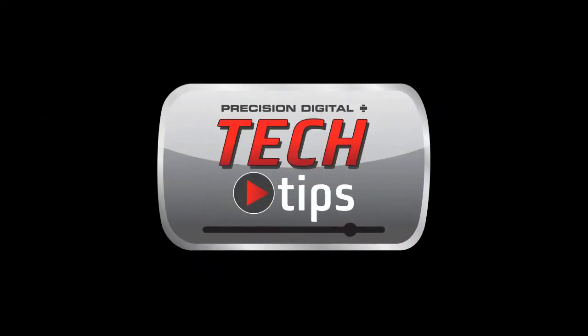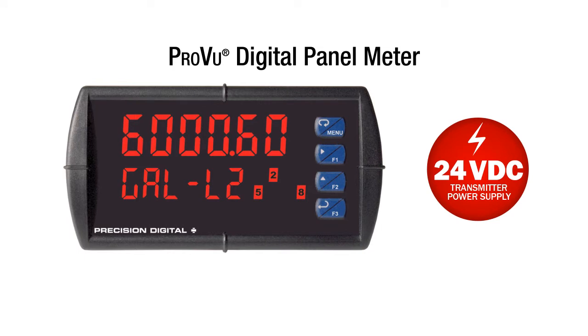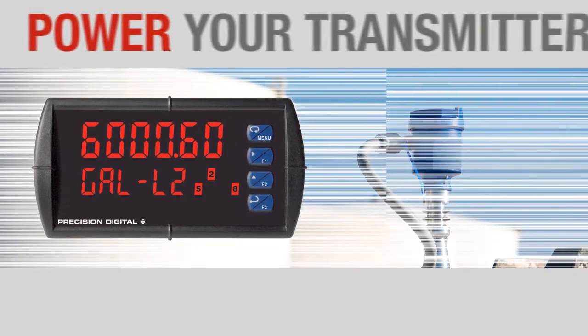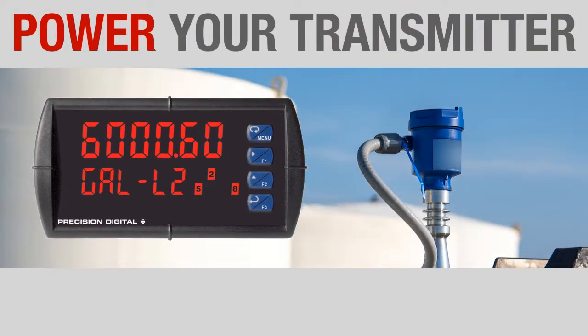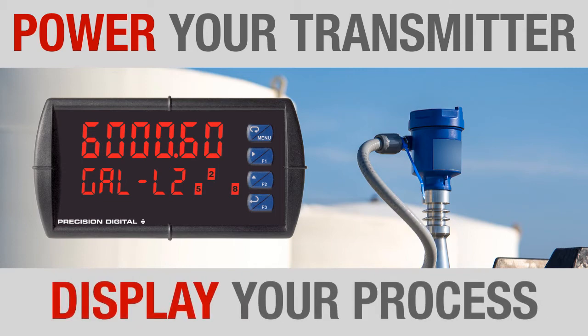Precision Digital Tech Tips. The ProVu digital panel meter includes a 24-volt DC power supply as standard. It can supply 200 milliamps, which is more than enough to power a 2-wire 4-20 milliamp transmitter and allow the ProView to display the desired process variable.